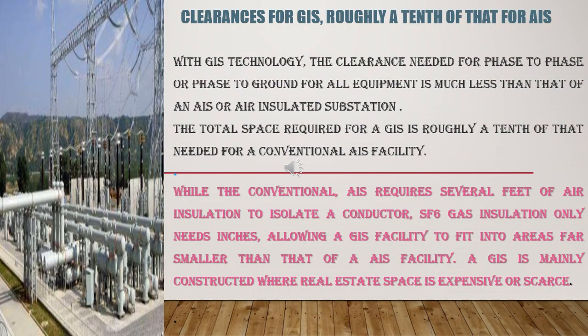Clearances for GIS, roughly a tenth of that for AIS. With GIS technology, the clearance needed for phase-to-phase or phase-to-ground for all equipment is much less than that of an AIS or air-insulated substation. The total space required is roughly a tenth of that needed for a conventional AIS facility. While the conventional AIS requires several feet of air insulation to isolate a conductor, SF6 gas insulation only needs inches, allowing a GIS facility to fit into areas far smaller than an AIS facility. A GIS is mainly constructed where real estate space is expensive or scarce.